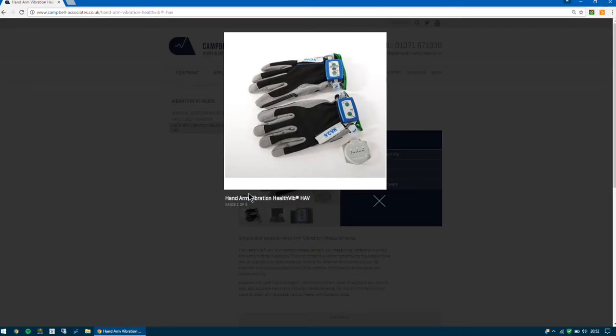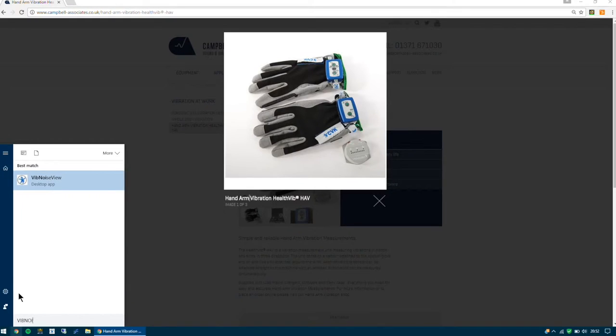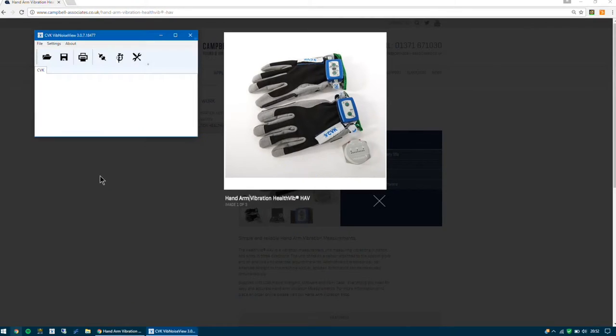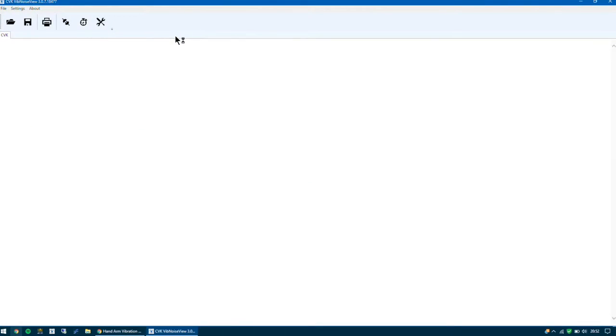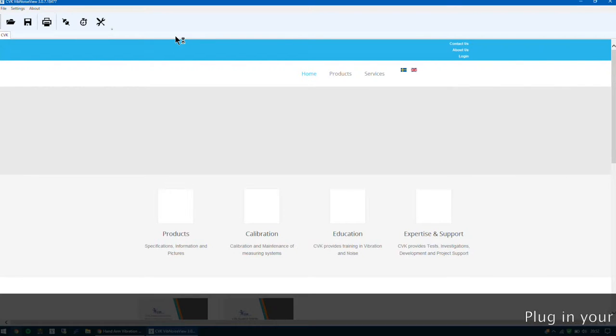In this video I'm going to show you how to download your CVK hand arm vibration measurement. To do this you will need the VibNoiseView software. It opens up as a small window — just enlarge that. You now need to plug in your Vib indicator.